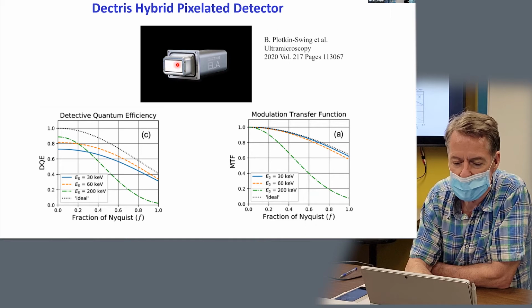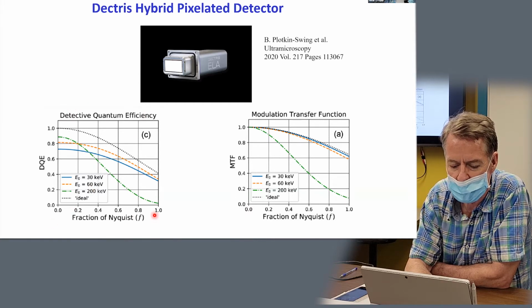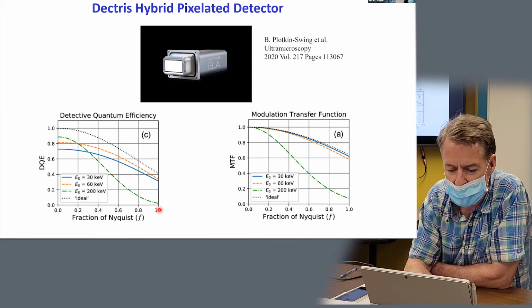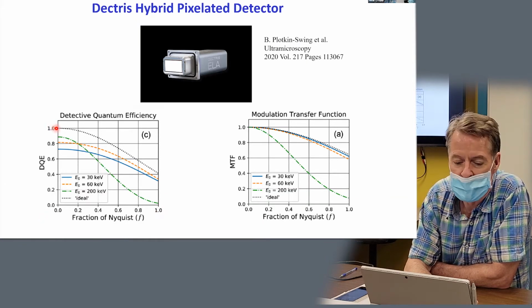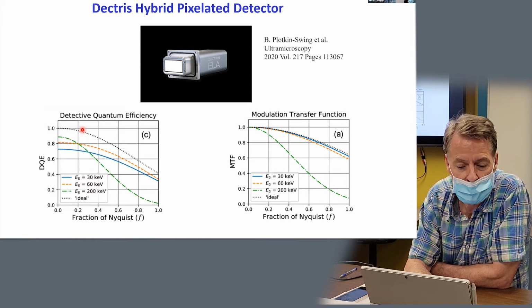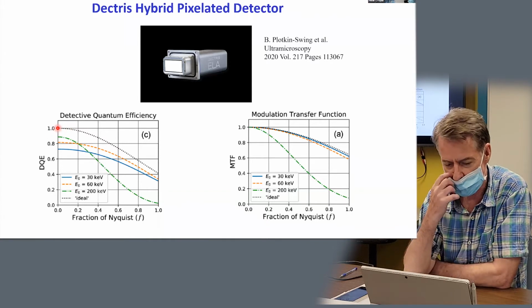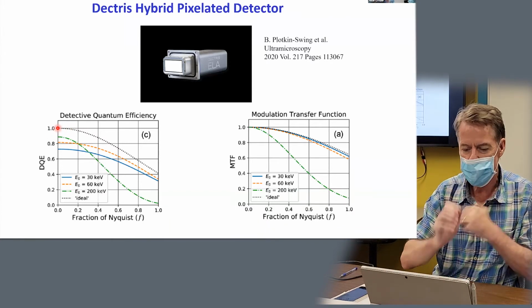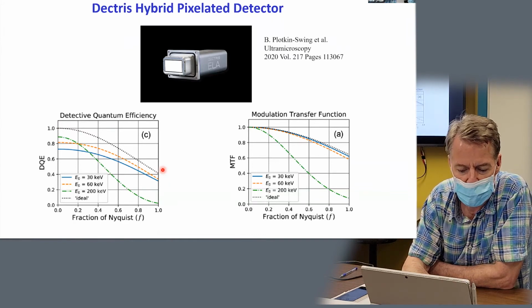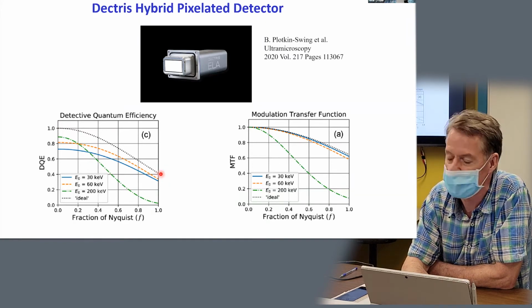This is the sensor element here. And again, a little bit of technical detail. This is a graph of the detector quantum efficiency as a function of spatial frequency, normalized to the Nyquist frequency. So Nyquist is over here. The black dotted curve is the theoretically best achievable ideal DQE, detector quantum efficiency. So it starts at 1 for spatial frequencies of about 0, and it drops to about 0.4. Those of you that know the Nyquist know that about 0.4 is the best you can get.